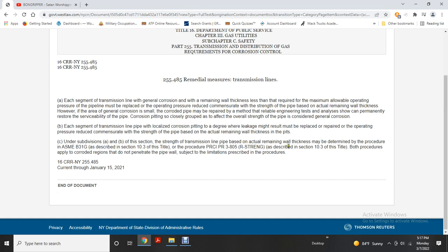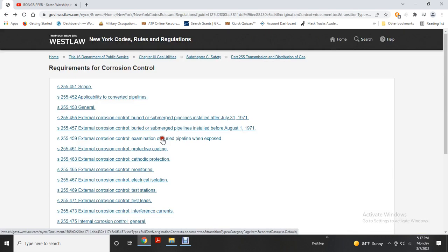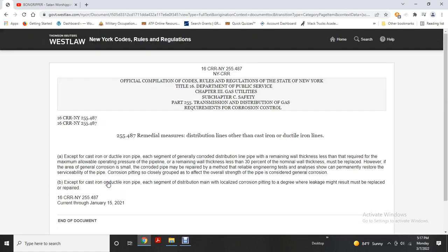The strength of a transmission line based on actual remaining wall thickness may be determined by procedures in ASME B31G as described in Section 10.3, or by PRCI PR 3-805 or R-strength procedures as described in Section 10.3. Both procedures apply to corroded regions that do not penetrate the pipe wall, within the significant limitations described in those procedures. For distribution lines other than cast iron or ductile iron, each segment with remaining wall thickness less than required for maximum allowable operating pressure or less than 30% of nominal wall thickness must be replaced. Where the area of general corrosion is small, the corroded pipe may be repaired by a method that can permanently restore serviceability. Corrosion pitting closely grouped to affect overall pipe strength is considered general corrosion.